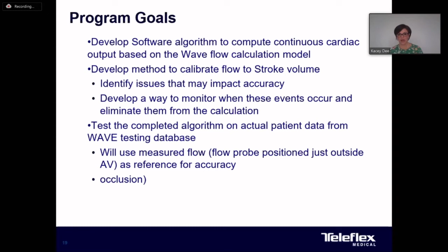This section now will discuss the basic concept of the flow calibration method for volume and share the initial test results with you from patient data stored from the original WAVE study. Now, the purpose in the development of this program is to calibrate the wave flow calculation for accurate volume. Currently, again, the flow calculated by WAVE is used only in the time domain. It does not provide accurate volume information. This project was designed to develop and test a method to calibrate the flow wave for volume. And once the calibration method was developed, it was tested using, again, actual patient data from the original WAVE study under a variety of clinical conditions.